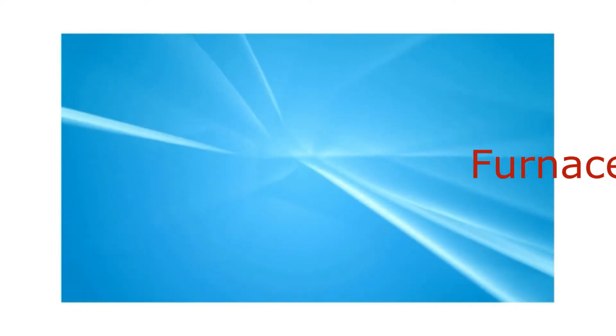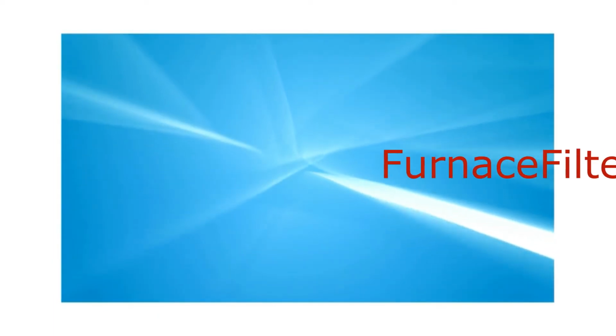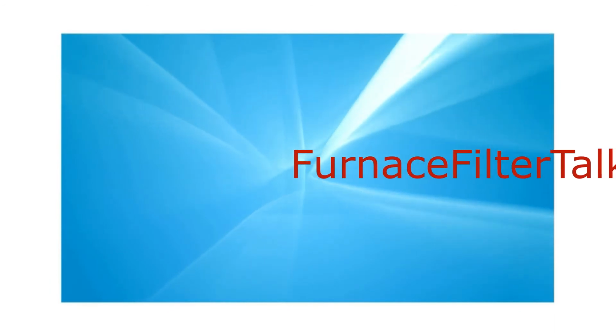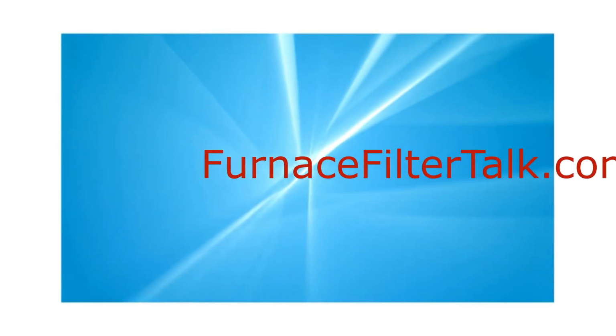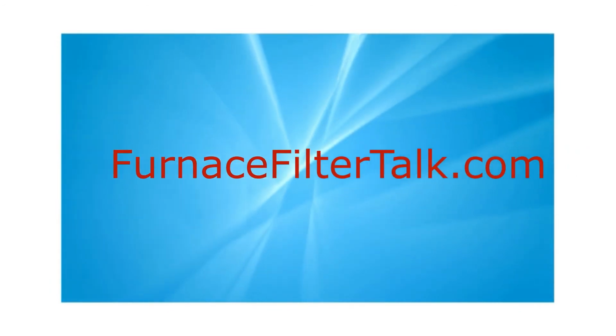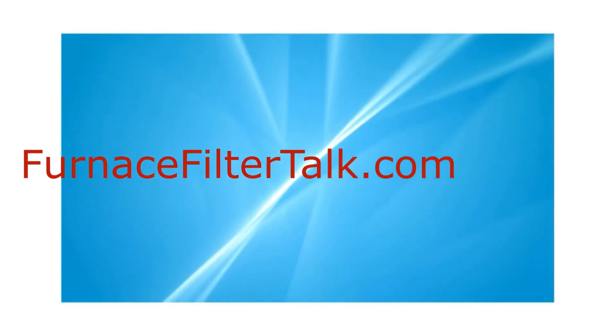MERV is the minimum efficiency reporting value and is the standard measurement in the industry for efficiency. Pressure drop is how the restriction in airflow is measured. Can a furnace filter be too restrictive? New filter. How do you know if the filter you buy is too restrictive? Asking your HVAC technician is one way, or consult manuals on your system.